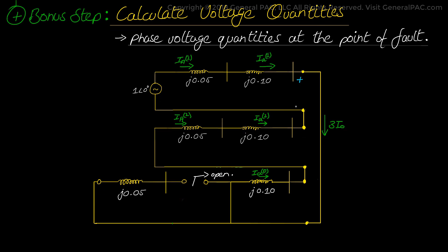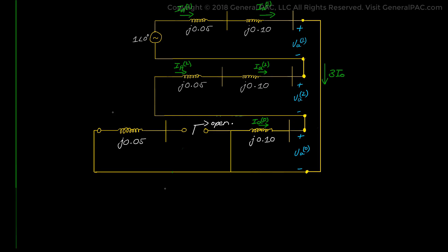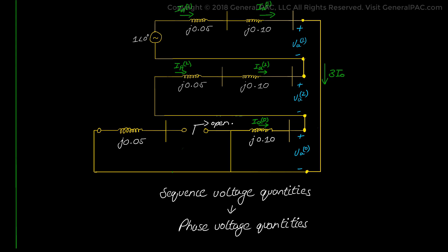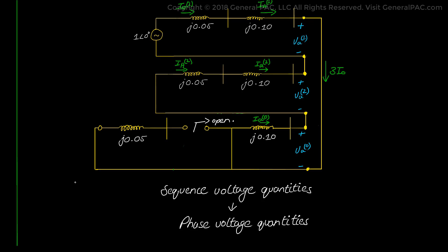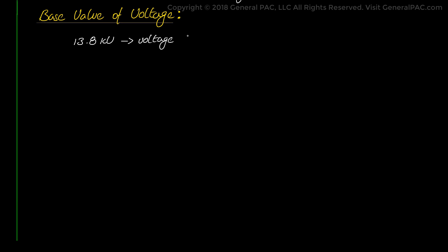We will go back to our fault sequence network and redraw it. In this figure, we want to focus on the positive, negative, and zero sequence voltages shown on the low voltage 13.8 kV fictitious bus. We want to determine the sequence voltage quantities by hand, and from those we will calculate the actual phase voltage quantities. Before moving forward, let's select a base value of voltage: V_base = 13.8 kV divided by root 3.